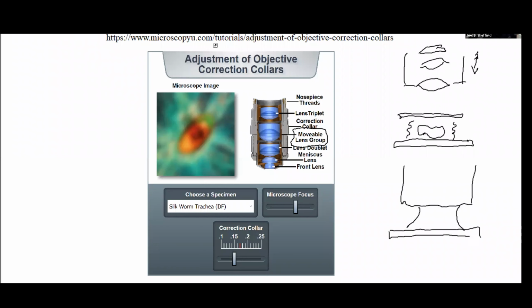And the refractive index of oil tends to match the refractive index of the glass, and the lenses are designed to compensate for what now becomes a fairly common correction. So you can just design those lenses one way. But if you're using one of these high resolution dry objective lenses, that's where the correction collar becomes an important function.